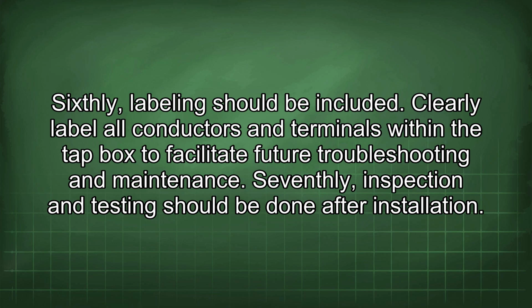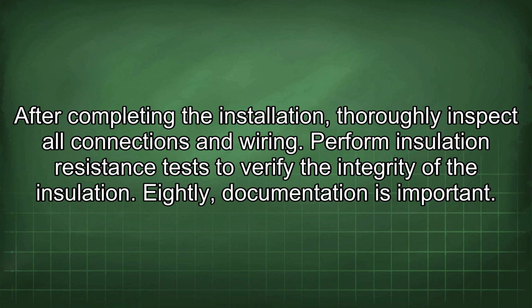Seventhly, inspection and testing should be done after installation. After completing the installation, thoroughly inspect all connections and wiring. Perform insulation resistance tests to verify the integrity of the insulation. Eighthly, documentation is important.